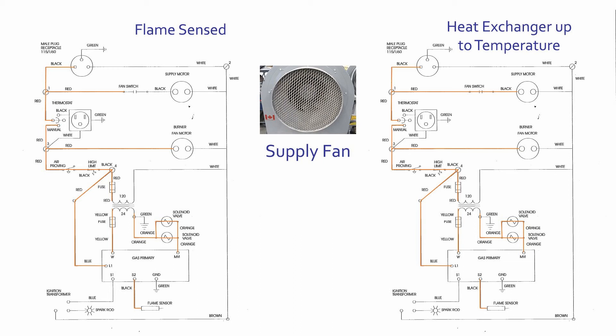When enough heat is produced in the combustion chamber to satisfy the fan switch, the fan switch will turn on the supply motor and the heater will begin to supply heat.